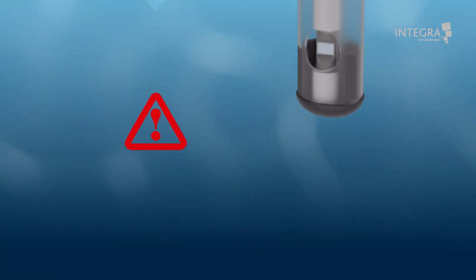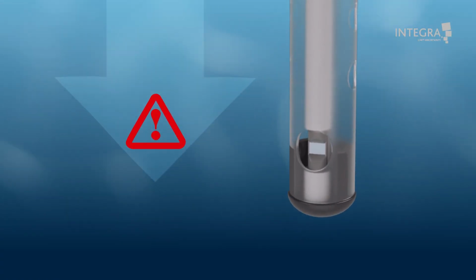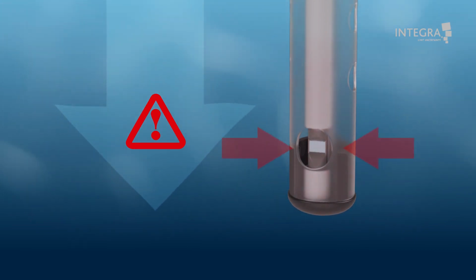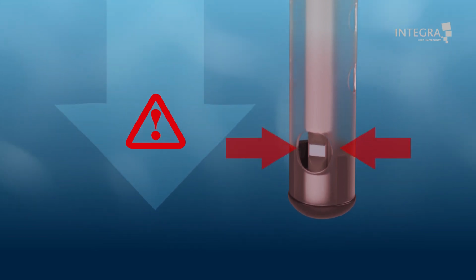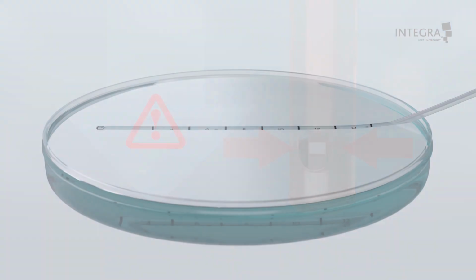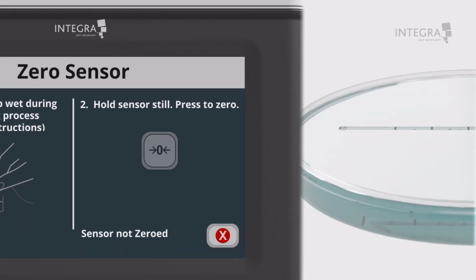Do not submerge the tip of the ICP sensor vertically in a deep pool of sterile water or sterile saline. Doing this will impose a hydrostatic pressure on the ICP sensor diaphragm that is higher than atmospheric pressure, resulting in an inaccurate 0 reference. Hold the sensor still without applying any external pressure to the tip apart from the sterile saline. If the device senses the sensor is moving, a 0 button will not be available.